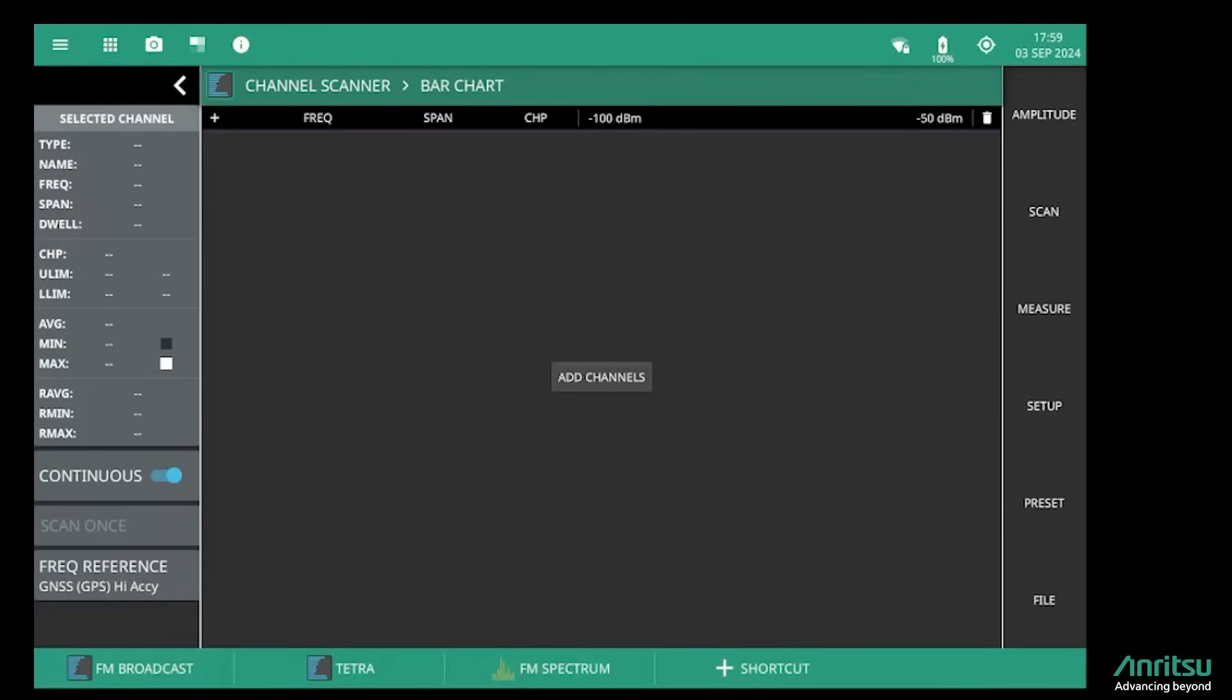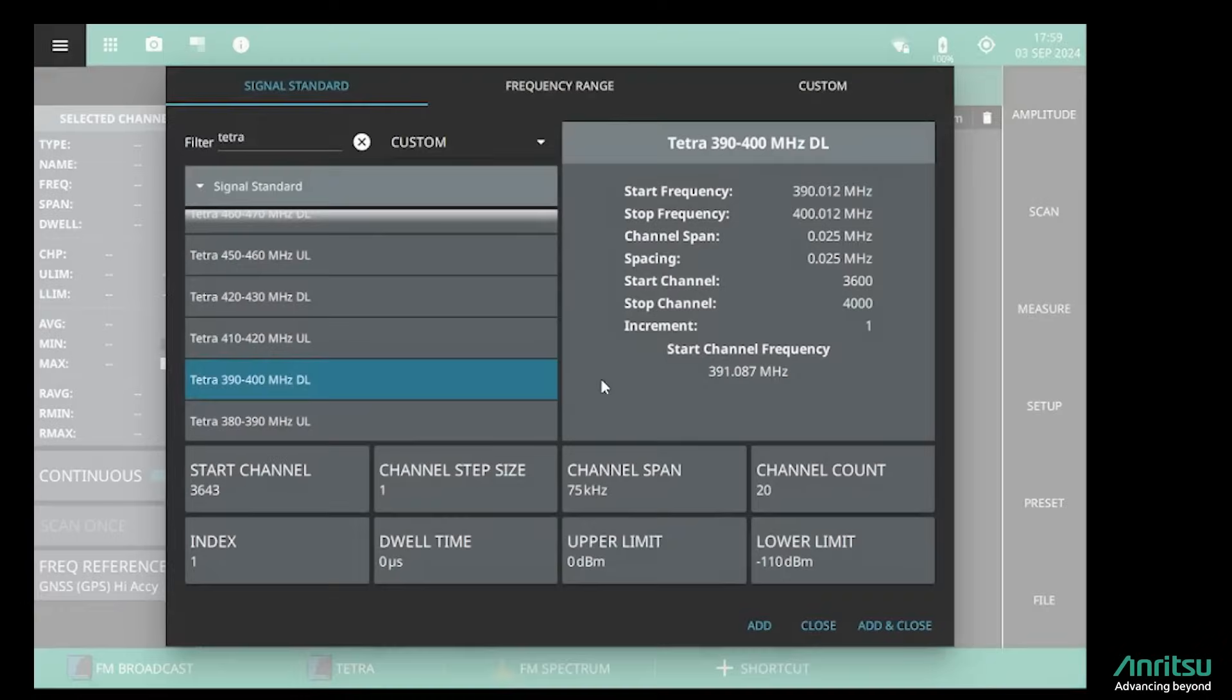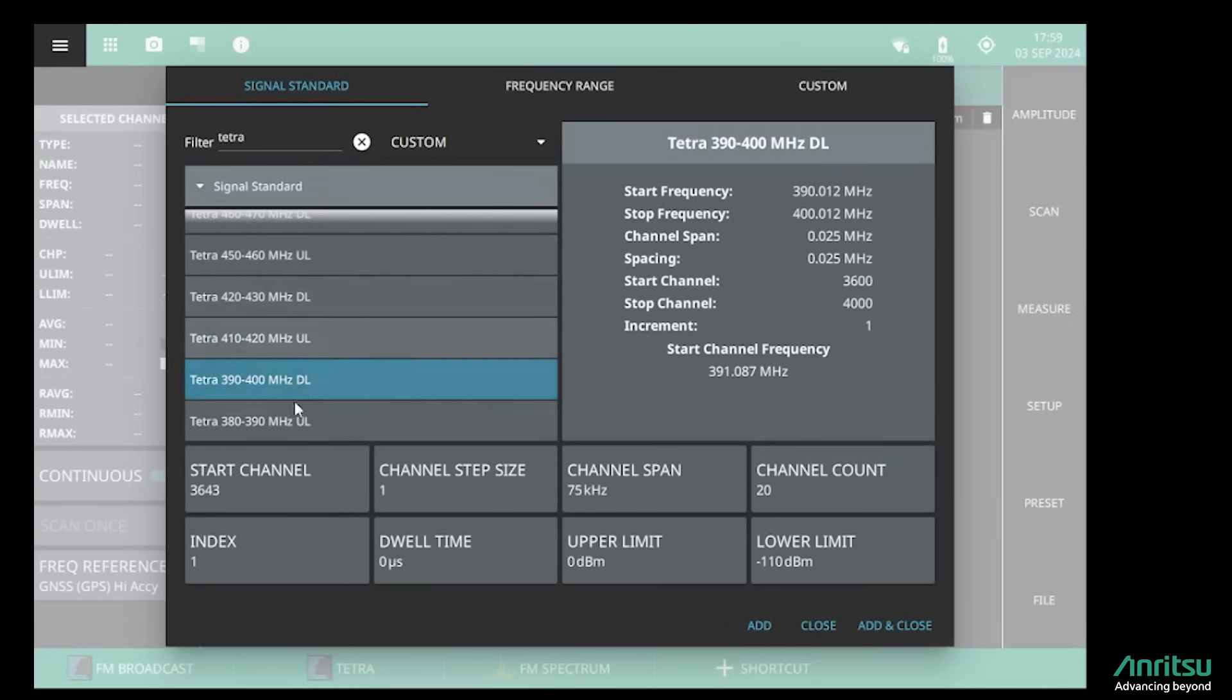I want to show you one other way that we can add channel frequencies in the channel scanner. If I go into the channel mode here, we can select different wireless standards. I've currently got it set to TETRA, and the instrument has pre-programmed channel plans for the internationally recognized TETRA bands. In this local area, the TETRA signals are in the 390 to 400 megahertz band.